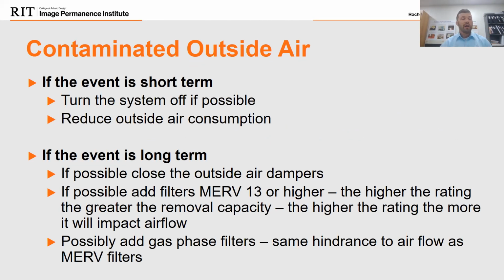What do I do? If it's a scenario like that, and it's after hours, look into turning the system off for just that short period of time that the fireworks are going off. Try not to bring in whatever pollutants may come from the fireworks. If it's a short fire, like, God forbid, a fire in a structure nearby, can we shut this system off for a little bit to not bring in whatever contaminants can be dumped in the air? If it's long-term, a major fire, something like that, is it possible to close the outside air dampers?